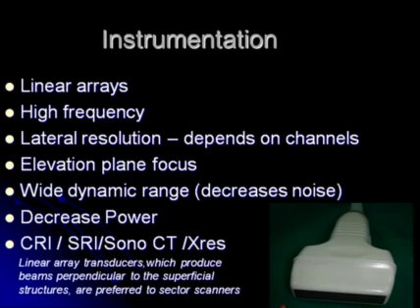We use linear arrays which are of high frequency, so good resolution, although the depth may be compromised. We have to make sure we have good elevation plane focus, use a wide dynamic range, and decrease the power. Multiple vendors have multiple post-processing tools that can also help in making the image better.